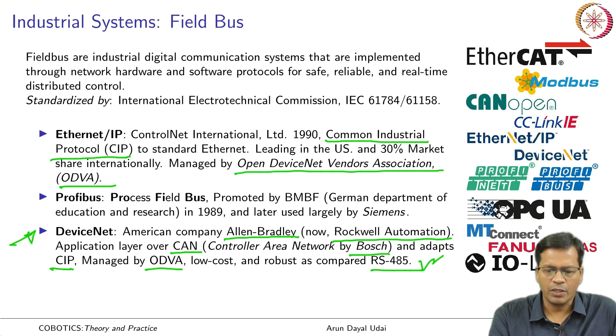DeviceNet is the next one, which is given by an American company, that is Allen Bradley. Allen Bradley again is now known as Rockwell Automation. They make PLCs, and they also make various other input output cards and drive systems. So, DeviceNet is an application layer over the CAN bus system, Controller Area Network, that was come up with by Bosch initially, and adapts the CIP. CIP is the Common Industrial Protocol. It adapts that, and this again is managed by ODVA, Open DeviceNet Vendors Association. They are robust as compared to RS-485. RS-485 was there in earlier days, it was a serial protocol and it became very popular because of its simplicity, but it has many safety concerns and security concerns also. So, that is the reason it was modified and adapted into different other forms.